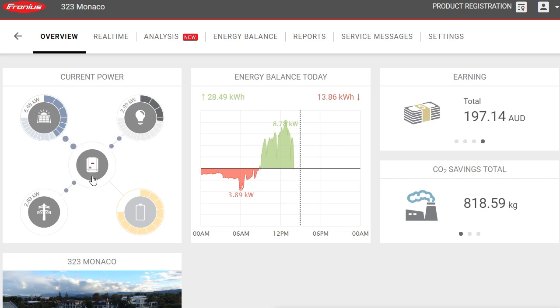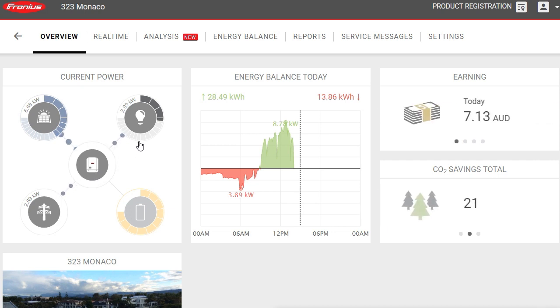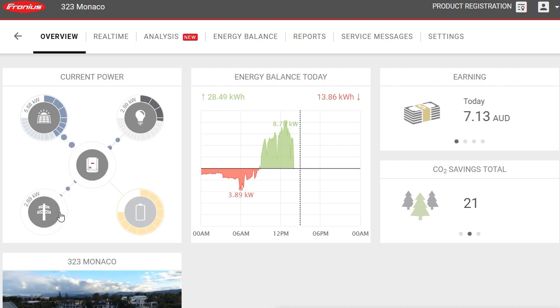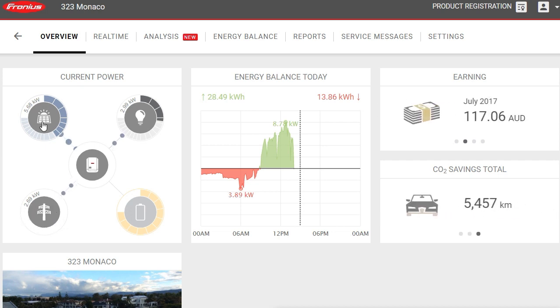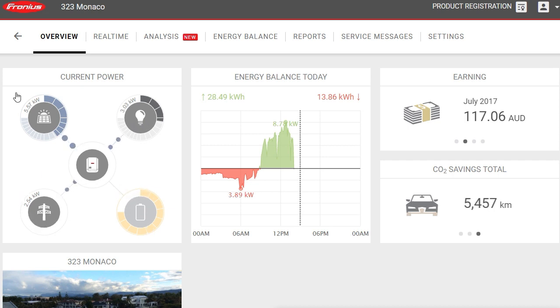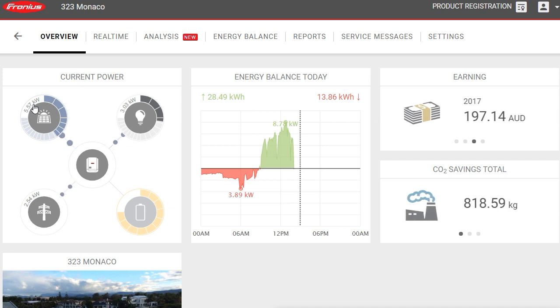From the inverter, 2.99 kilowatts is going to the loads in the property, represented by the light bulb, and 2.69 kilowatts is surplus solar power being sent back to the grid. If there was a battery and it wasn't fully charged, the surplus would go to the batteries first, to maximize self-consumption, rather than being exported to the grid.